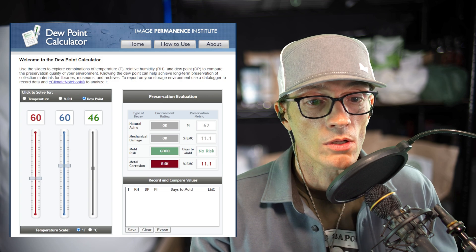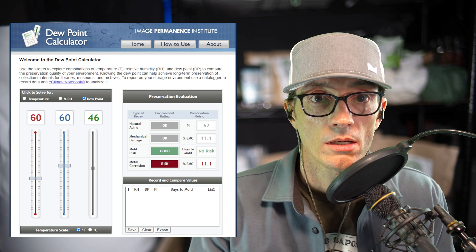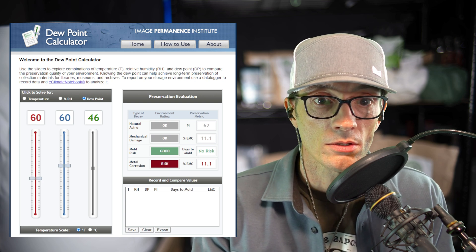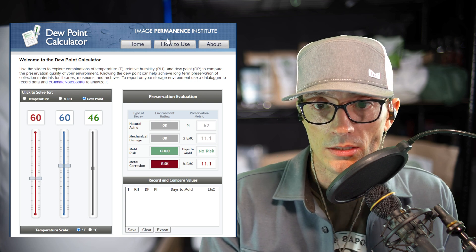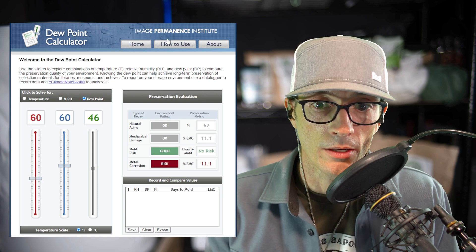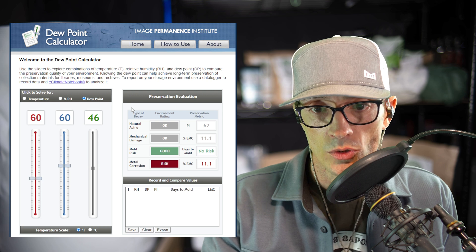Alright, it's time to talk about dew point. We do get into some nuances here. Firstly, if you're just monitoring humidity and keeping it below a safe range like 60%, you're just fine, you're likely not gonna have any mold. But what I'm saying is you're not dialed in. Relative humidity is relative—it's determined by how much heat is in the room, then you can find the humidity measurement. It's a lot of variables, it's not simple. What you want is something absolute. Dew point is the amount of moisture in the atmosphere irrespective of the temperature. I'm gonna show you a website I've gotten a lot of positive feedback on over the last couple years. It's called dpcalc.org for dewpoint calculations. We've got it pulled up for 60-60, typical dry range. 60-60 gives you a dew point of 46 degrees.